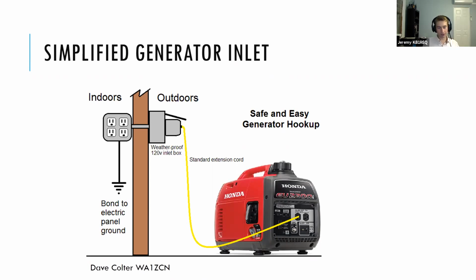What you're essentially building here is an extension cord into your house or into this building. You have a weatherproof inlet on the outside. You run some conduit, some Romex, and you have some outlets on the inside. Now, unless there's a generator plugged in, those outlets aren't doing anything. But if you lose power, you bring your portable generator there, you plug it in, and you have power at those outlets.